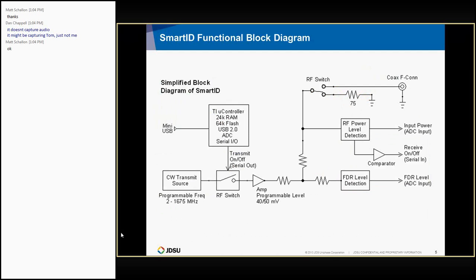And this is the block diagram. It's a very simplified block diagram that just shows the essential functions that the SmartID deals with. The main elements that I'm trying to point out here: it's a smart device. It has a TI controller on it. It has a continuous wave, or a sine wave transmit source with a programmable frequency from 2 to 1675 megahertz. The RF switch is used for signaling between the probes, basically telemetry, and it runs nominally at 125 kilobits per second. That's the serial I/O that turns it on and off.